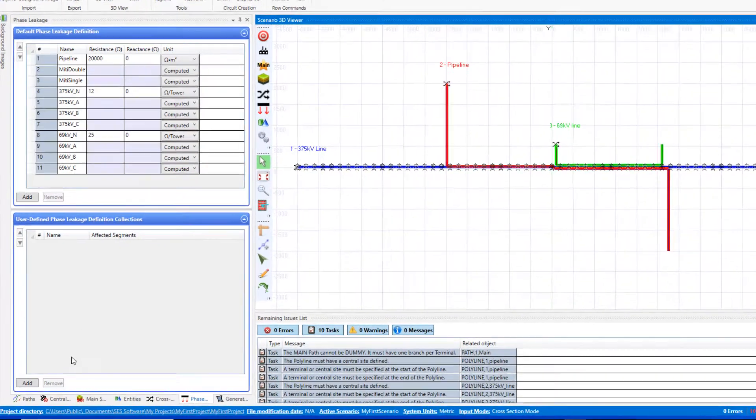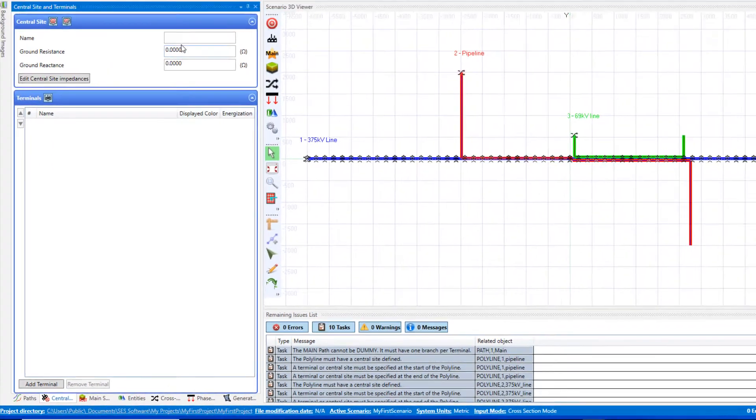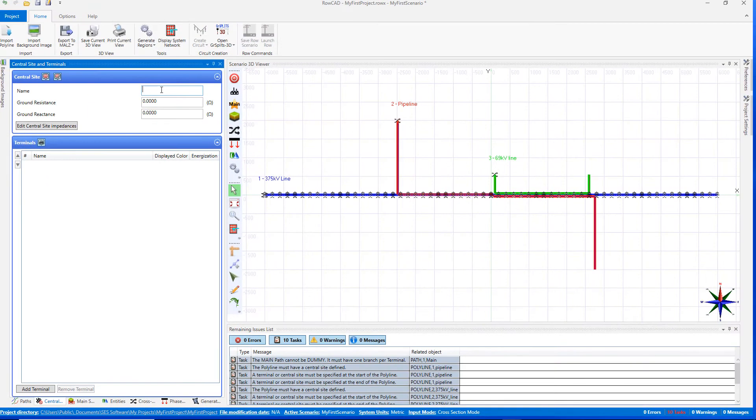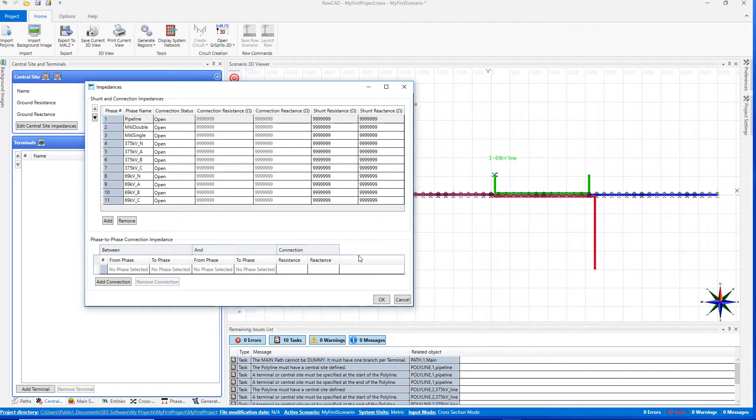For the next step, click on the Central Site and Terminals tab. Enter Central Site Name, Ground Resistance, and Reactance. Click on the Edit Central Site Impedance button for the definition of the grounding and connection impedances of all phases at the central site.